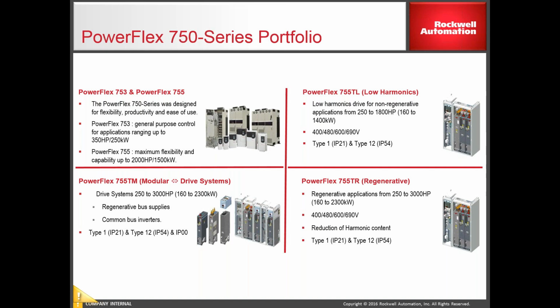The second option is the TR, 755TR. That's a regenerative drive. Okay, it still has the low harmonics, but it's a regenerative drive that goes up to 3,000 horsepower. The low harmonic drive, the TL, only goes up to 1,800. The TR goes up to 3,000.